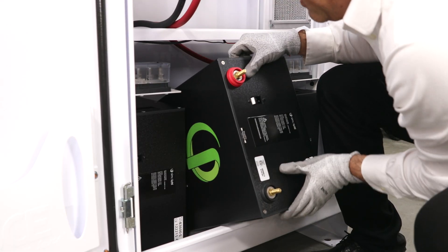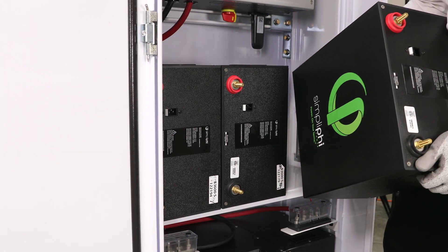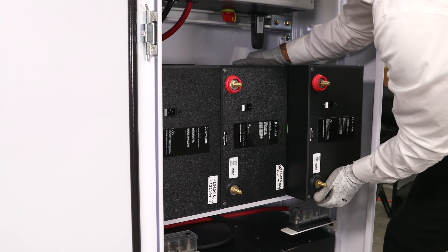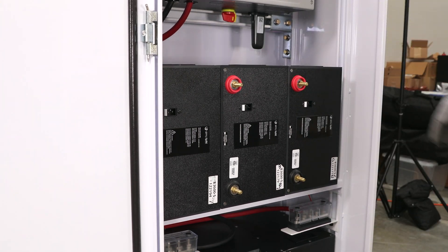Place three 53.8 batteries in the bottom of the cabinet and arrange three 53.8 batteries on the Access's top shelf. Orient the modules so that the battery terminals point toward the Access door, with the negative posts nearest the bottom of the Access enclosure.